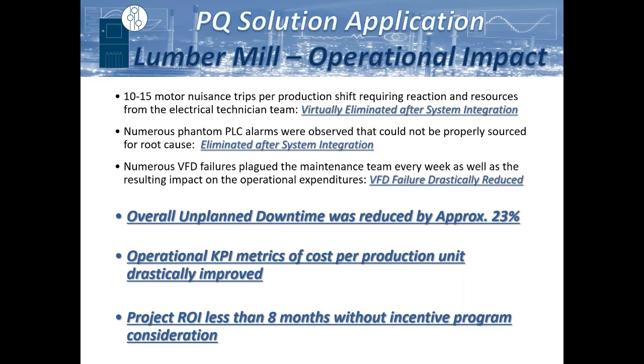After we stabilized that voltage and got that voltage in its optimal region, now all of a sudden those were virtually eliminated. They also had phantom PLC alarms that they could never explain. As soon as the network was stabilized, all that went away. They had numerous VFD failures every single week. All of a sudden, that was drastically reduced.